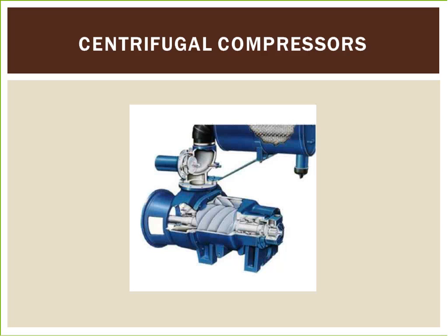These types of compressors are also designed for higher capacity because flow through the compressor is continuous. Adjusting the inlet guide vanes is the most common method to control capacity of a centrifugal compressor. By closing the guide vanes, volumetric flows and capacity are reduced. The centrifugal air compressor is an oil-free compressor by design. The oil-lubricated running gear is separated from the air by shaft seals and atmospheric vents.